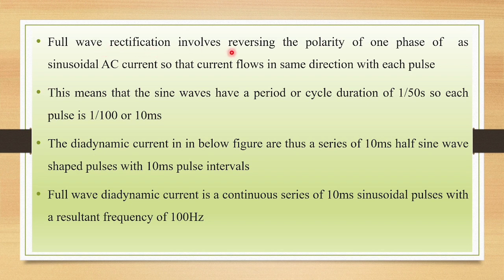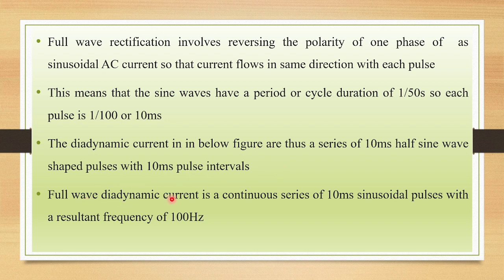Full wave rectification involves reversing the polarity of one phase of sinusoidal AC current so that the current flows in the same direction with each pulse. The sine waves have a cycle duration of 1 by 50 seconds, so each pulse is 1 by 100 or 10 milliseconds. The diadynamic current is a series of 10 milliseconds half sine wave shaped pulses with 10 milliseconds pulse intervals. The full wave diadynamic current is a continuous series of 10 millisecond sinusoidal pulses with a resultant frequency of 100 Hz.